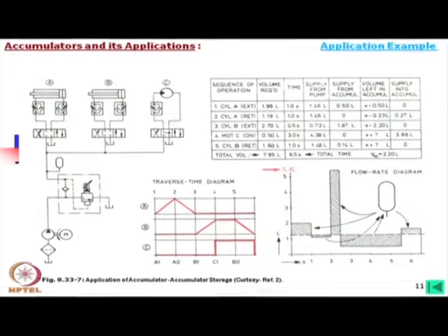again a return of V 1.06, and this is the chart, you can follow this chart, and then what is there. So, total volume requirement will be there and time etcetera all, and it is found that 2.20 liter is the working volume, keeping that as a working volume, and 10 liter, that what we have seen, 10 liter accumulator size is suitable.